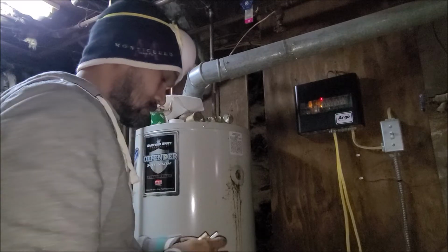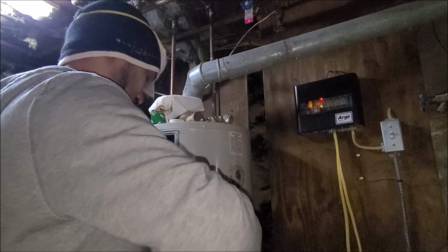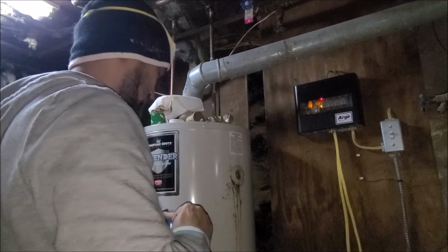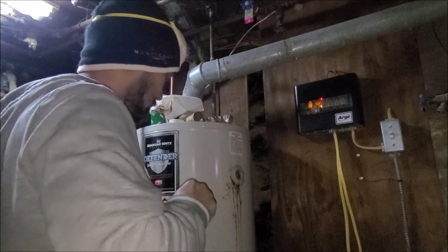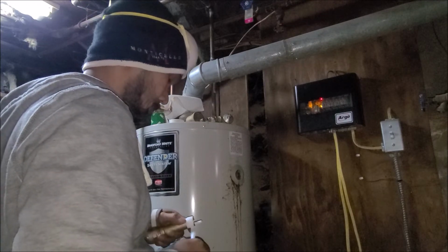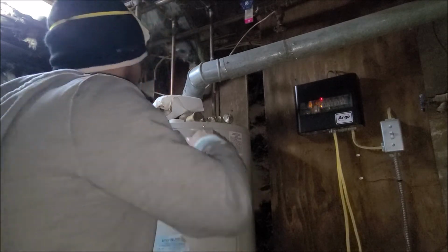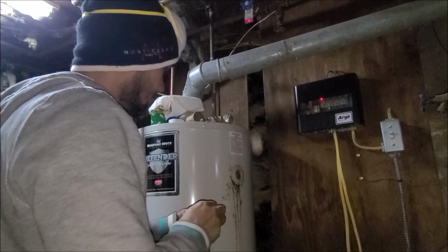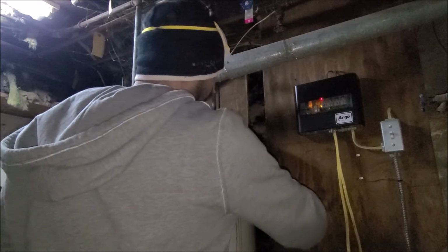Like I said, I hope this will do the trick. This is too much pressure, and it wasn't working properly because you didn't check the pressure relief valve at least once a year. Now it will cost you like $600 instead of $18.